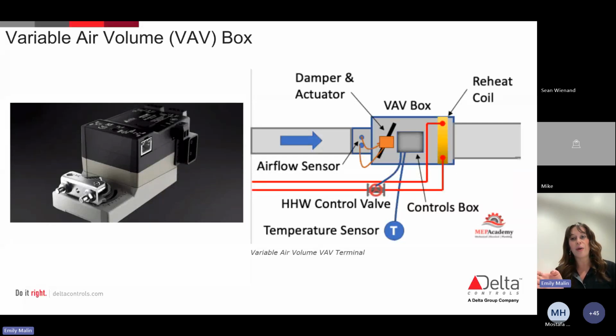Our reheat coil there at the end is optional, but it can add warmth if it's needed. It's being supplied by our hot water control valve there on the bottom. And then finally, we have a temperature sensor. That temperature sensor is going to be sitting inside of a zone that is controlled by the VAV. It's sensing the environment of your building, signaling to the system whether or not it needs to make adjustments.